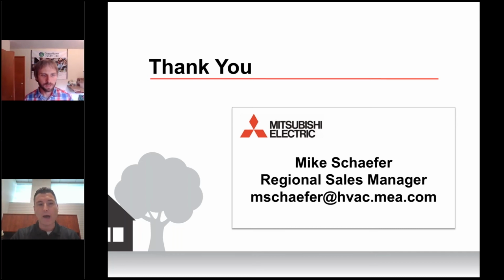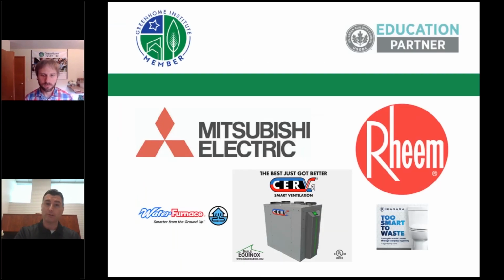It's the compressor heating output, its ability to continue to remove heat from outside without overheating, and when it's too cold, trying to remove too much heat. So you have a much more efficient compressor. The efficiency ratings on a cold climate heat pump are generally much higher than a standard heat pump, and this relates to not only heating but cooling as well. Your SEER ratings on those systems are generally higher, so you're getting higher heating and cooling efficiencies.